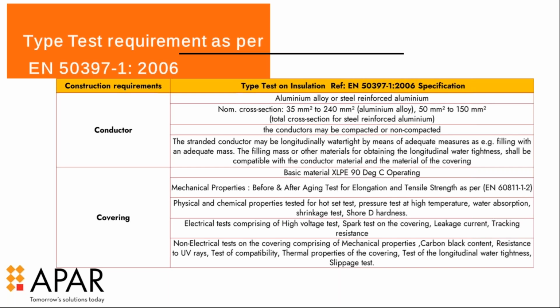And the electrical tests comprising the high voltage test, spark test on the covering, the leakage current, which I've already talked to you about. It should be less than 1 milliamp in the case of the covered conductor as per the EN standards. And the tracking resistance test. Then non-electrical tests on the coverings: mechanical property, carbon black content, resistance to UV rays, test of compatibility, thermal properties of the covering, then the test on longitudinal water tightness, and the slippage test. These are the tests commonly done in this EN standard 50397, and this makes this technology very foolproof, to be used for at least 30 to 40 years in your network without any problem if it is properly done.